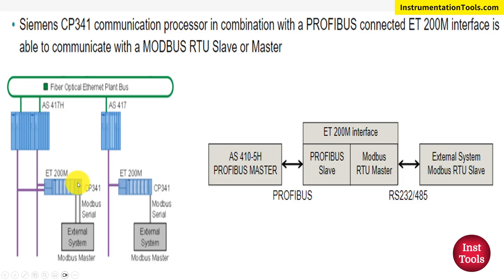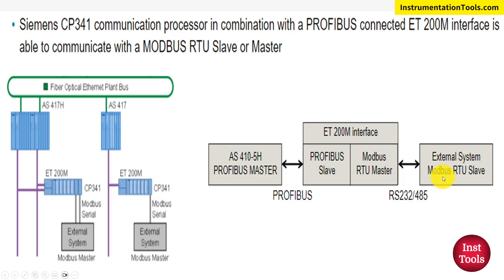Here we can see the CP341 card, which acts as the Modbus RTU master. In Modbus communication, slaves hold the data and the master requests the data from the slaves. This connection is a serial RS-232 or RS-485 connection. For example, a Modbus slave device such as a pH meter stores the process variable data. The CP341 card acts as master, pulls data from the active slave device, and stores it in the ET200M CP341 card. It also acts as a converter.